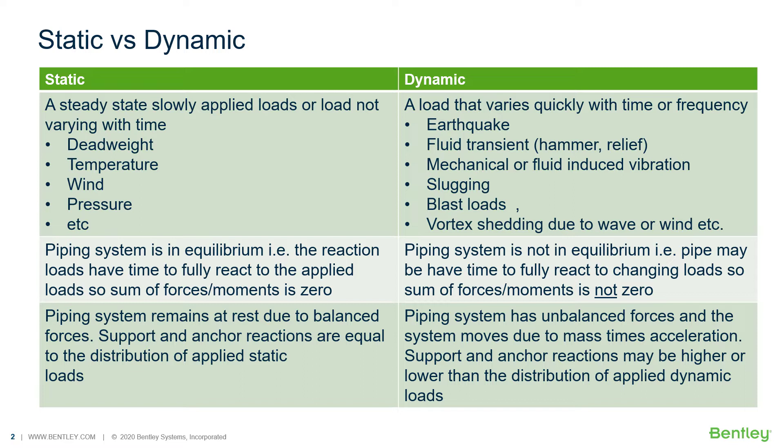In static loading, the piping system remains at rest due to balanced forces, so the support and anchor reactions are equal to the distribution of the applied static loads, whereas in dynamic loading, the piping system has unbalanced forces, and the system moves due to mass times acceleration. The support and anchor reactions might be higher or lower than the distribution of the applied dynamic loads.